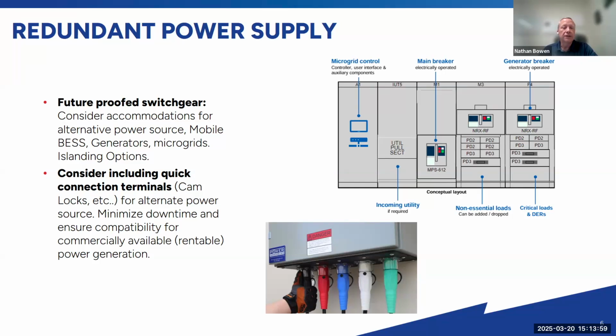Another thing I'd consider in an installation, to make it easier to tie into redundant power supplies, is quick connection terminals or cam locks. There are different brands—Hubbell has a twist lock. Most major commercial rental places use cam locks on larger wattage generators, battery energy storage, and similar apparatus.